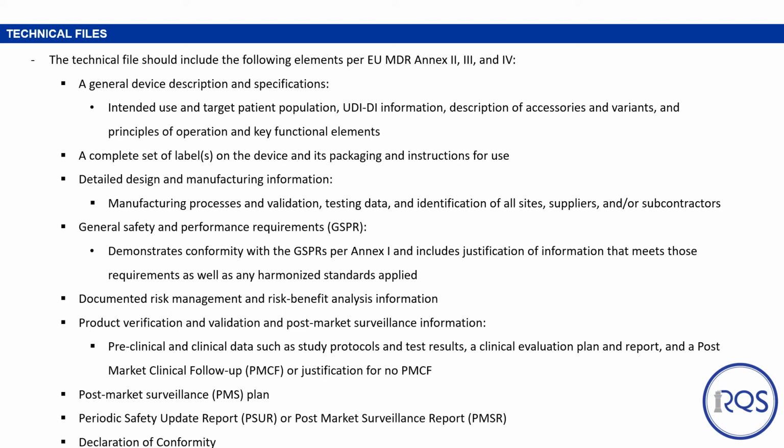And this includes preclinical and clinical data such as study protocols, test results, a clinical evaluation plan and report, a post-market clinical follow-up, or PMCF, and/or justification for no PMCF. The technical file should also include a post-market surveillance plan and a periodic safety update report, or post-market surveillance report, depending on the classification of the device, as well as a declaration of conformity.